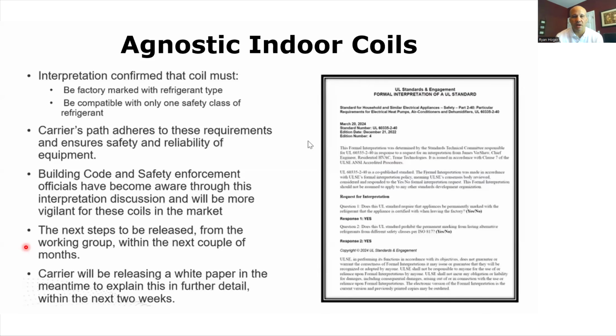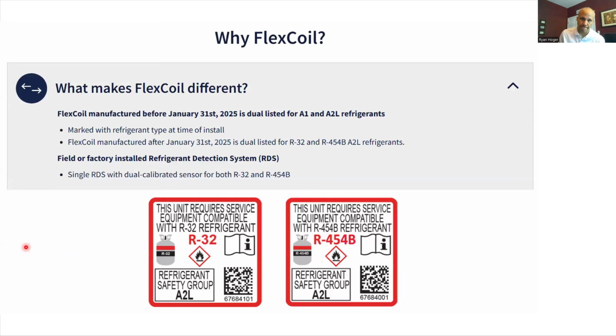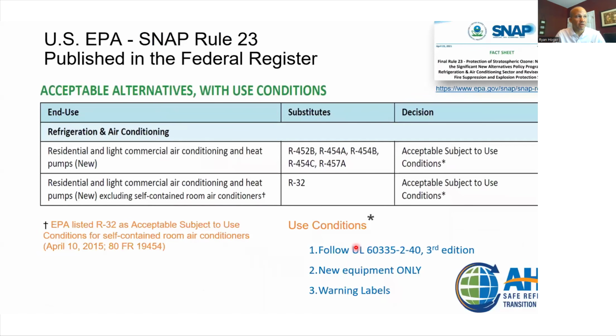So instead, the compromise is that ADP makes two versions of those coils now. They make one for non-A2Ls, so one coil for 410A and R-22, and you tell them what expansion device you want, and then a separate coil for R-32 and/or R-454B combined. You still tell them what expansion device you need, but it comes with the safety controls related to that. And when you get that coil, they give you two stickers in the box, 32 and 454B, and you stick the one on there that you actually installed, so that the guy servicing it behind you knows what's going on.